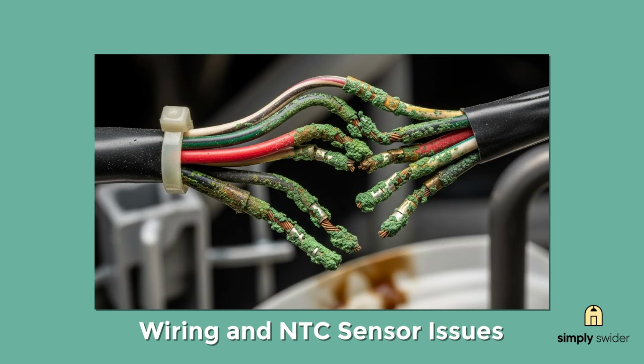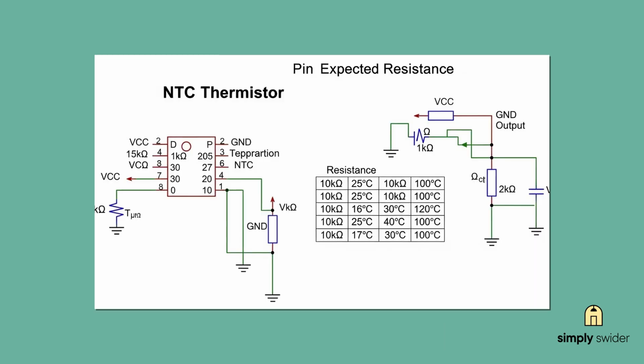Another thing that'll trigger E09 is faulty wiring or a bad temperature sensor. I had this customer last month who was convinced her heat pump was dead, but it turned out to be corroded connections from a small leak that happened months earlier. The NTC sensor, that's the temperature sensor, can send bogus readings to the control board and make it think there's a heating problem when there isn't. Look for loose connections, corrosion around the terminals, or any signs of water damage in the wiring harness. If you see green corrosion on those connectors, clean them up with some contact cleaner.